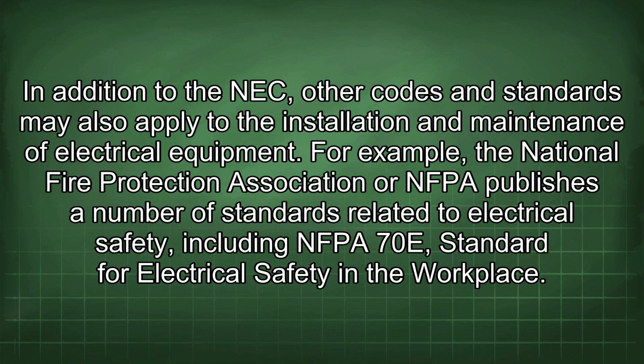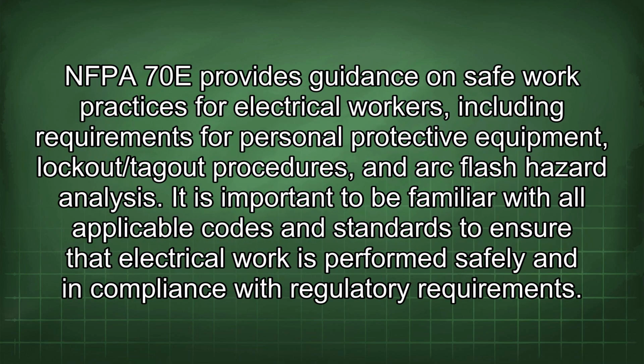In addition to the NEC, other codes and standards may also apply to the installation and maintenance of electrical equipment. For example, the National Fire Protection Association, or NFPA, publishes a number of standards related to electrical safety, including NFPA 70E, Standard for Electrical Safety in the Workplace. NFPA 70E provides guidance on safe work practices for electrical workers, including requirements for personal protective equipment, lockout/tagout procedures, and arc-flash hazard analysis. It is important to be familiar with all applicable codes and standards to ensure that electrical work is performed safely and in compliance with regulatory requirements.